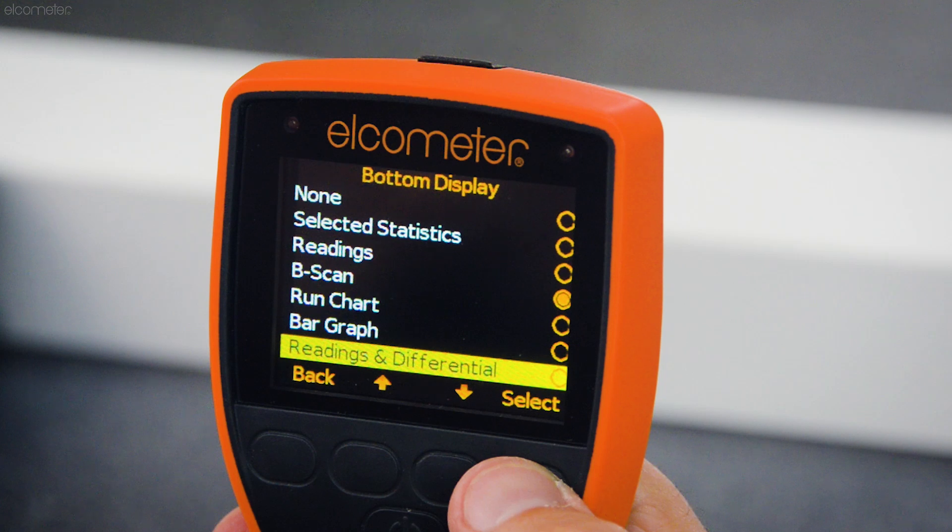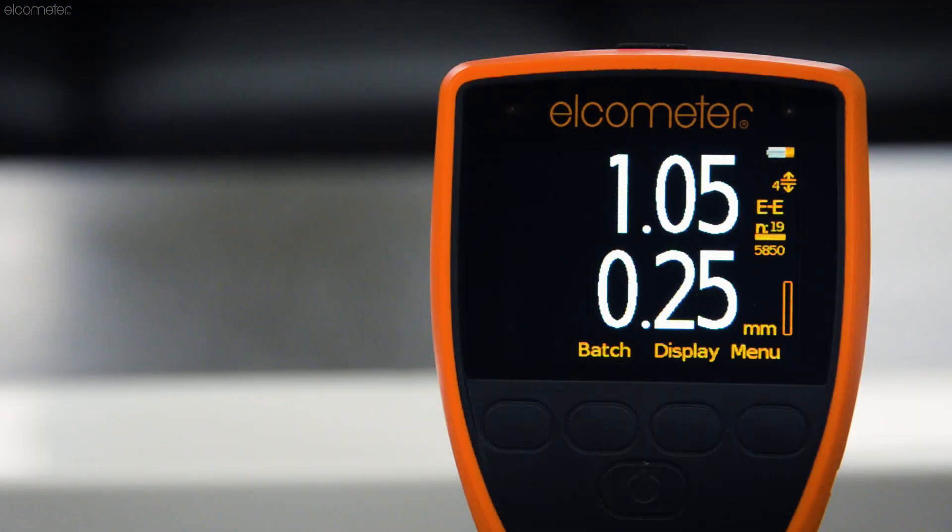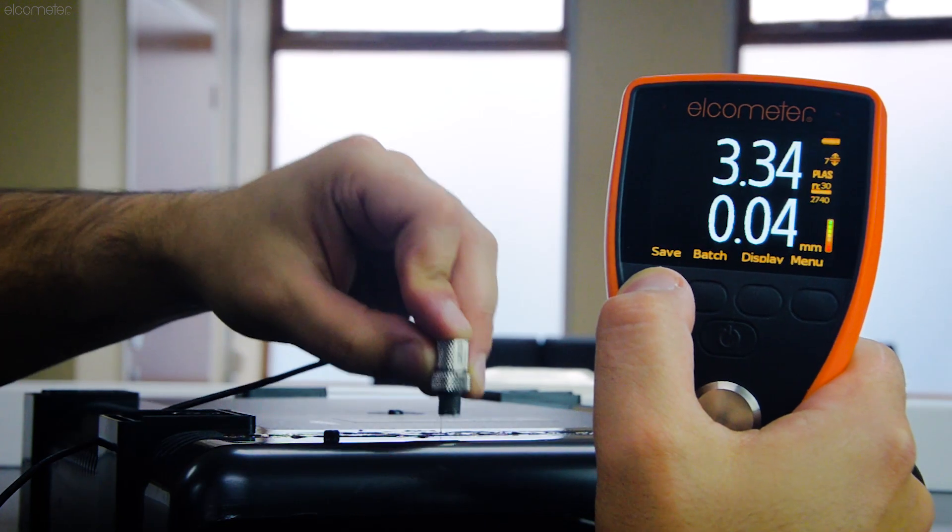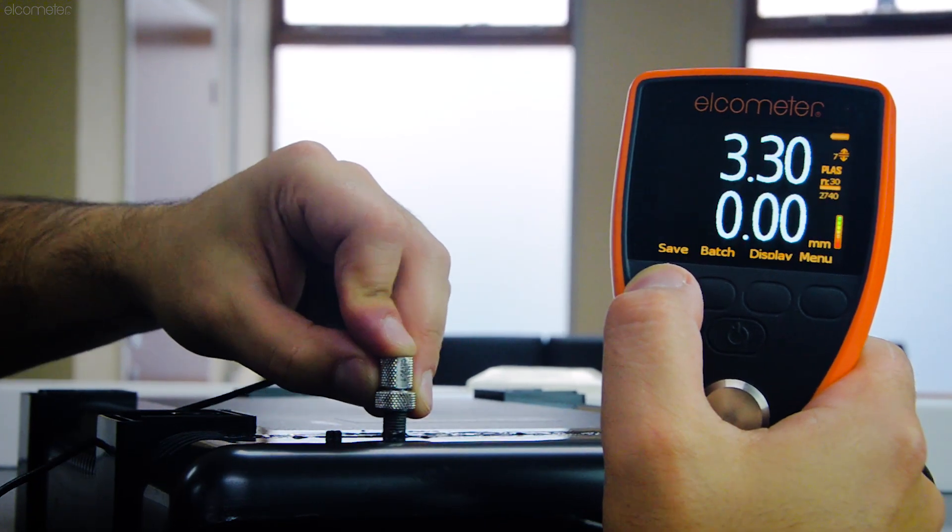Alternatively, differential mode displays the last reading and how much it differs from the user-definable nominal value, also known as the target thickness, indicating where the material is thinner or thicker than expected.